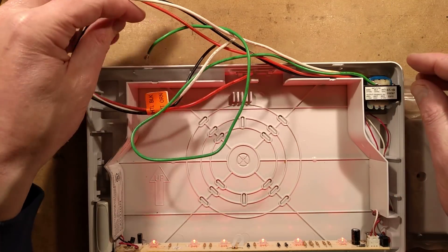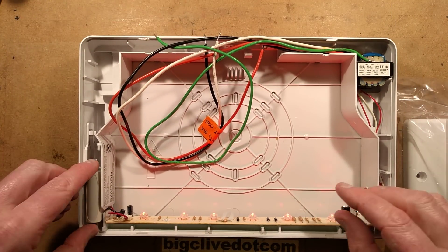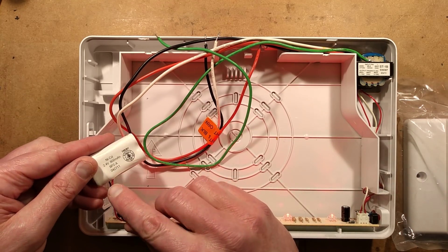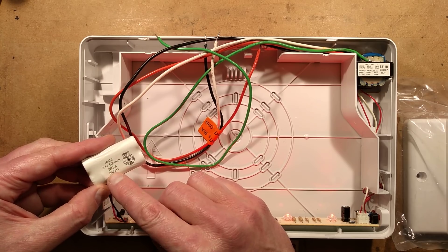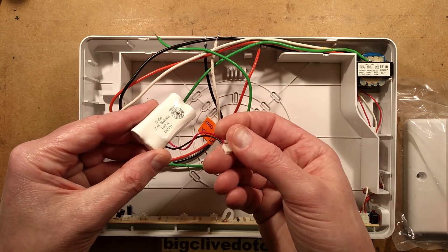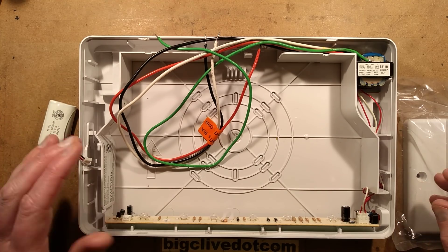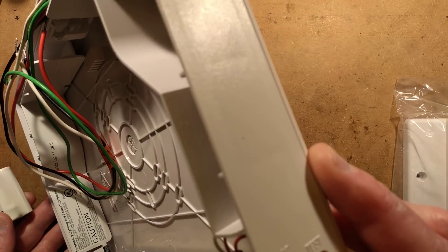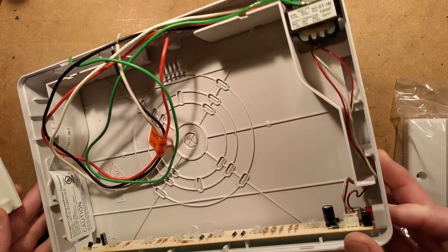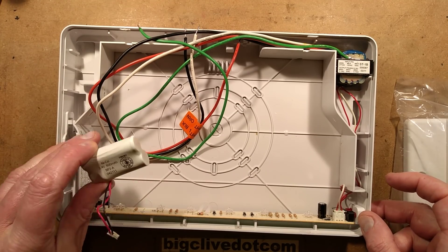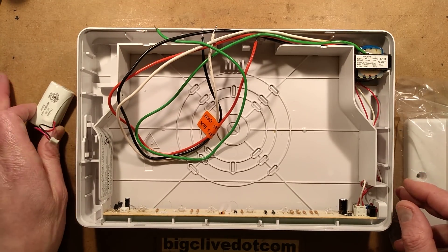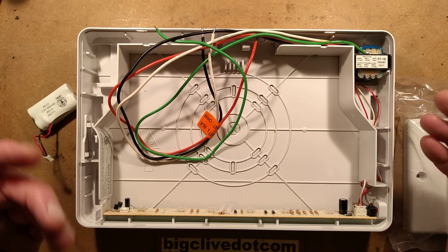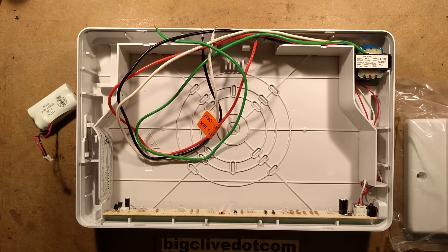Now past that morbid story, let's look at the power supply. When lit off power, it has a couple of double-A sized NiCAD batteries, 600 milliamp. The unit has a test button and a little light to show it's on. When you press the test button, it simulates power failure and the fitting switches to battery operation. To test long-term operation, you'd turn the power off completely, pretty much what you do with UK ones.